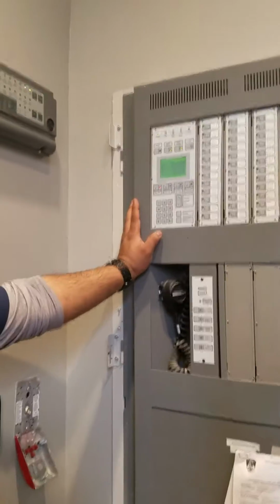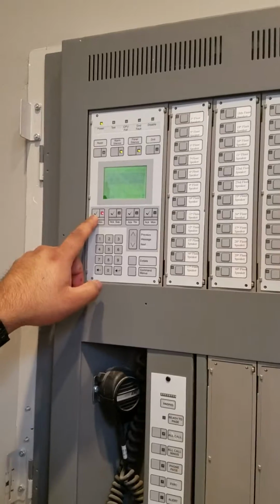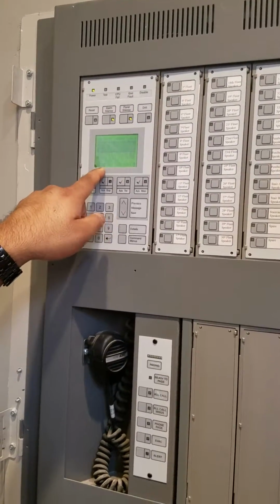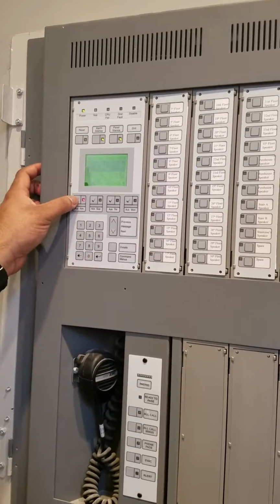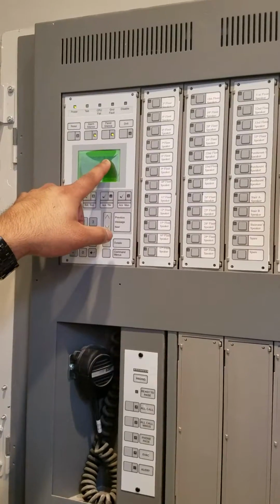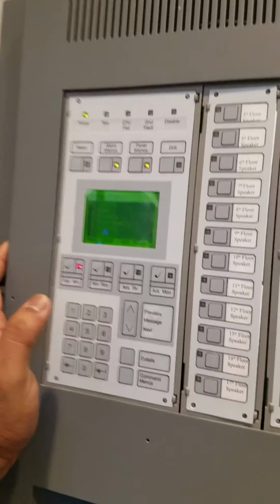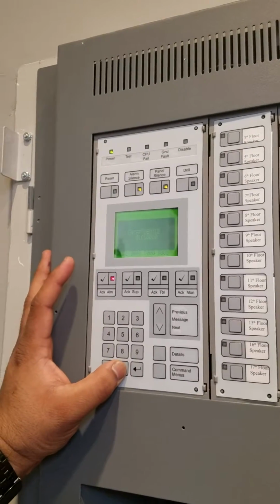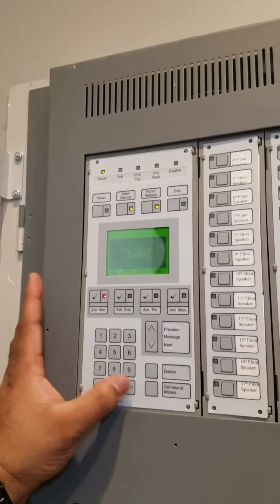So how we do that is we'll go to command menus. Oh, first we want to see the point, right? Because you need the point to disable it. So you would make sure that you're on your alarms category, Alarm A is highlighted, and we would hit details. So your point would be 01, 04, 0172, right? Then you would go to command menus. You will go to disable. You want to disable that device, right? 01 is already there for you. So at that point you would enter 04, 0172, and then you would hit enter.